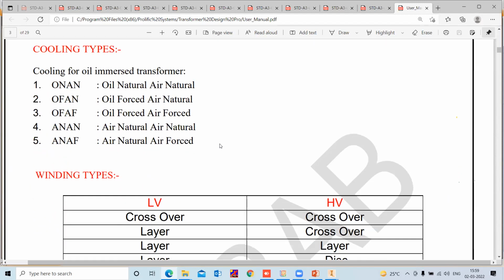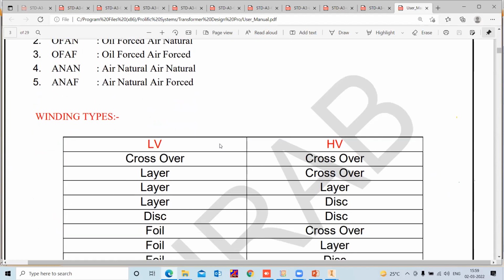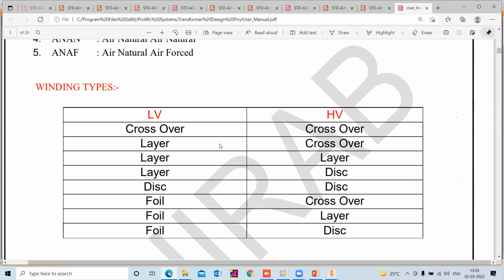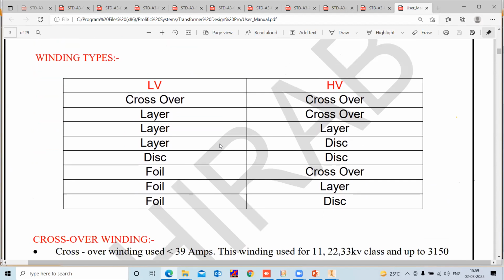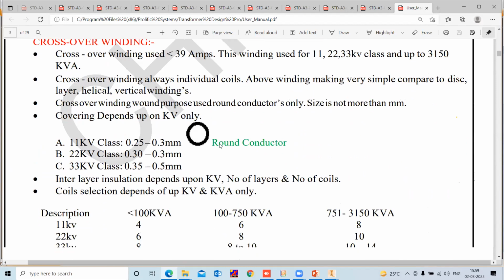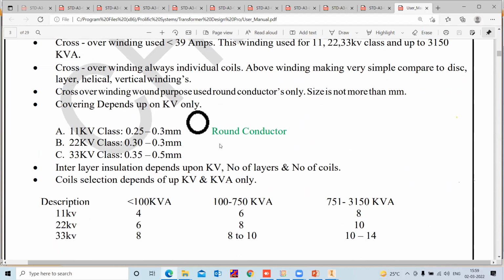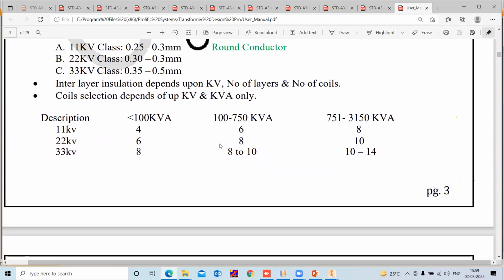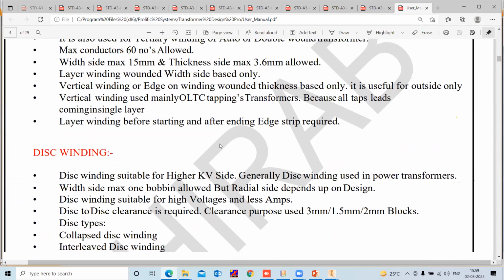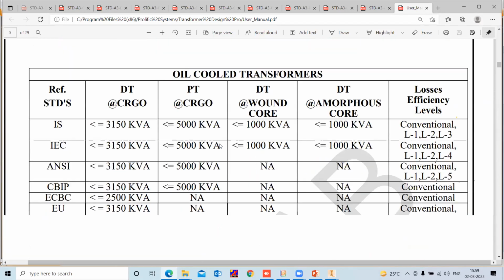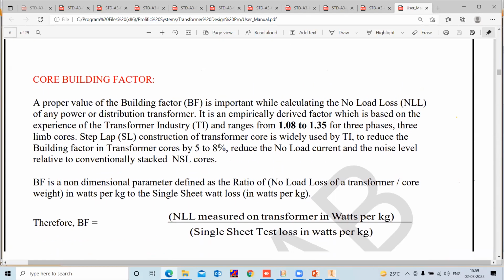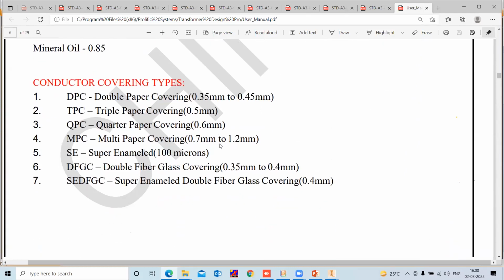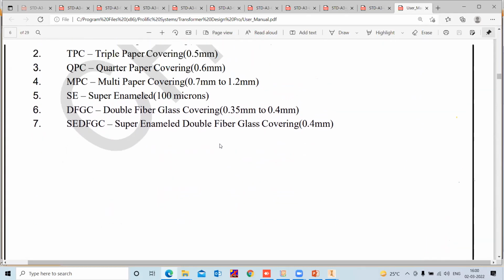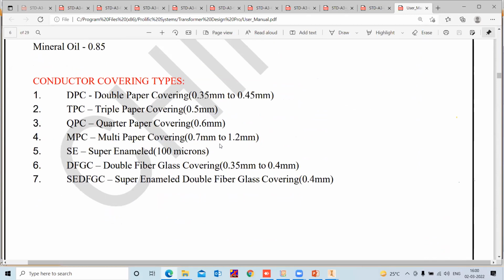Same for the cooling types. The full form of coolings we have given here. Then the suitable winding types. For LV and HV, we have 7 types of winding combinations as per the current. And that winding type we have explained here. Then the interlayer winding, disc winding, then the material suitability for dry type and oil type, then core building factor, then the material densities for weight calculation, then conductor covering types. There are all types of conductor coverings like super enamel, then for dry type you'll get a DFGC.